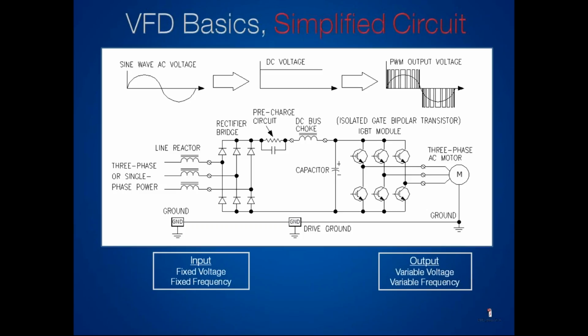The reason we convert AC voltage to DC voltage within a drive is so that we can better control the actual speed of the motor, or the frequency that's being output by the drive, okay? So in that rectifier bridge, we convert AC voltage to DC voltage. That DC voltage is then stored in the capacitors, okay? Now this is where it gets kind of interesting because in the capacitors, we still have to give voltage to our motor, right? So the DC voltage is being stored in those capacitors. You see those little 6 round things on the right-hand side of the drive? Those are called IGBTs. And basically those IGBTs are sort of acting as little timers.